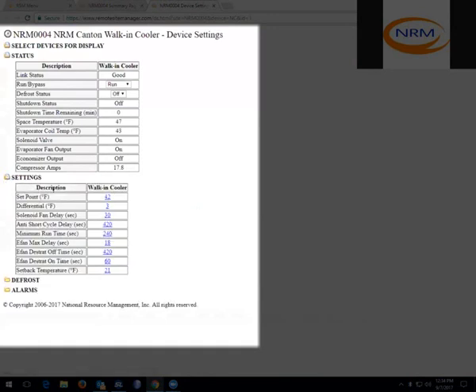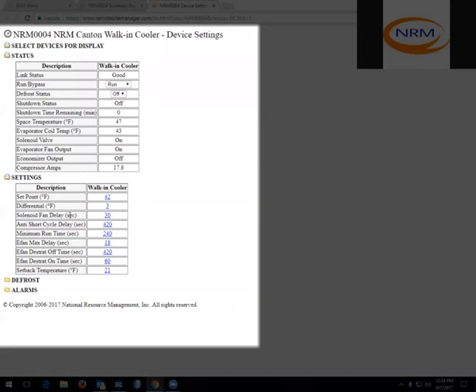So you have your basic settings, which is setpoint, differential, solenoid fan delay, anti-short cycle delay, minimum runtime, evaporator fan max delay, evaporator fan destratification off time, evaporator fan destratification on time, and setback temperature.